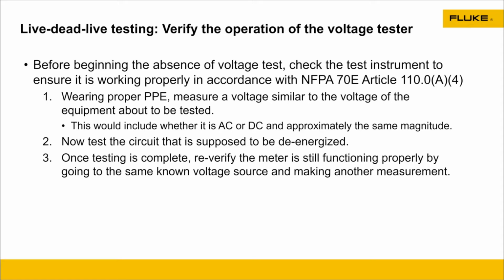So we do this by going to a known voltage source. We know that this outlet is 120 volts. We're going to use our DMM. We're going to check it. We're going to see 120 volts on the line. Now, also part of this is to go back to the breaker and turn that off. And we're going to check that circuit again and know that our meter read 0. And then finally, we're going to re-energize that line, go back to the meter, back to that circuit, and validate, yes, our meter is truly working correctly. We can go through our day and make that measurement.